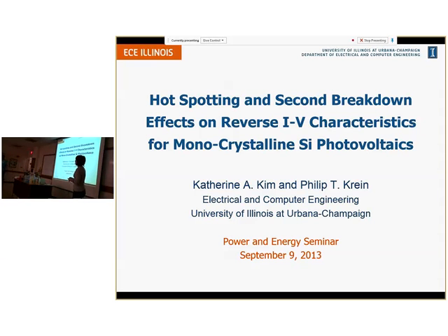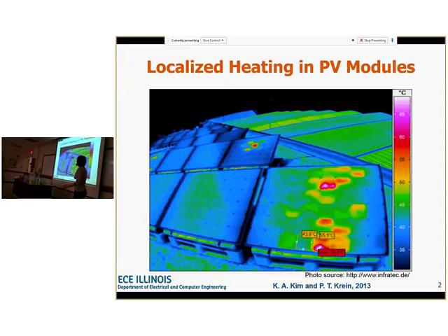So despite the long title, we're looking at hot spotting within cells. Specifically, I'm looking at monocrystalline photovoltaic cells. One of the things that happens, and this is a really cool group, I think they're in Denmark, is they do thermal imaging of larger pictures. You can see a big array of panels, but within some of them, we get these little hot areas. For example, on this one and up here, we have certain cells that reach a higher temperature.